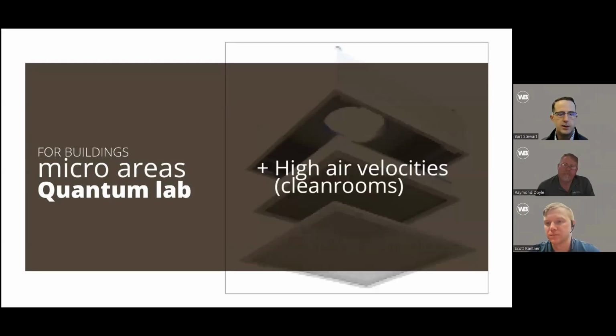So then the last thing Scott touched on briefly: with clean rooms comes high velocity air, and with high velocity air comes a source of vibration. So designing those clean rooms in such a way that you get the volume of air you need and the cleanliness you need from the filtration, without creating vibration on your table, is a whole specialty.